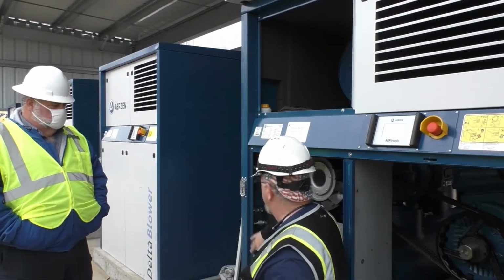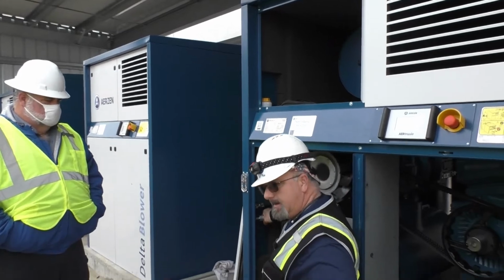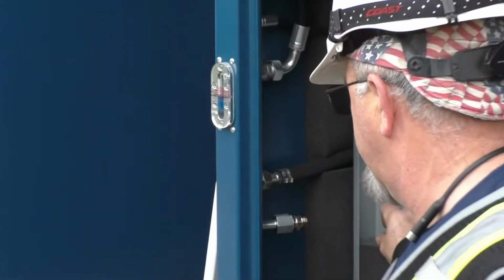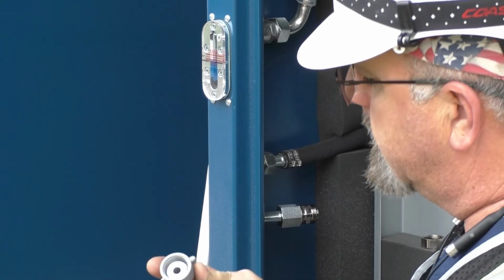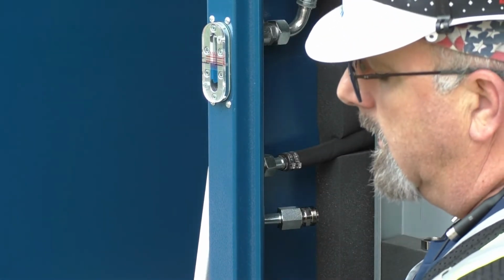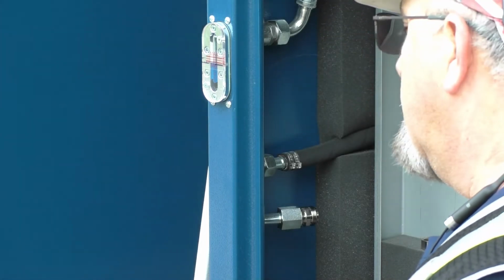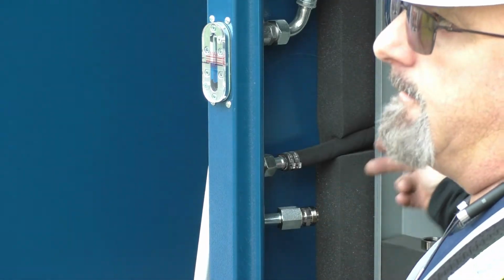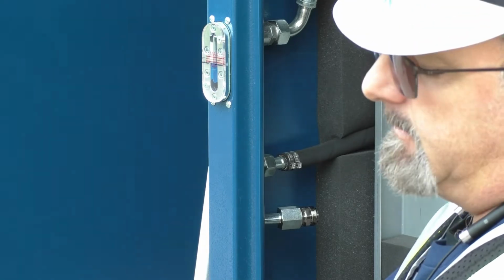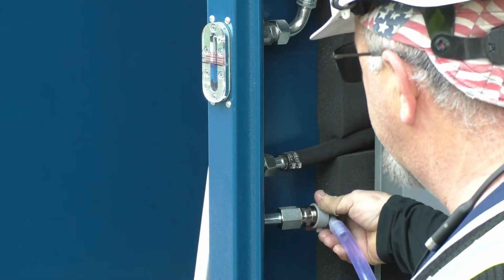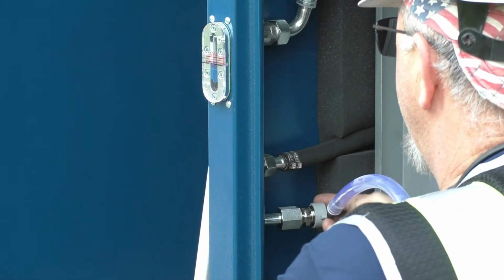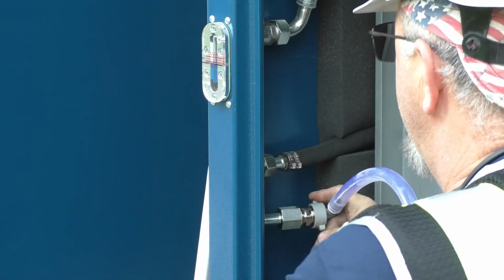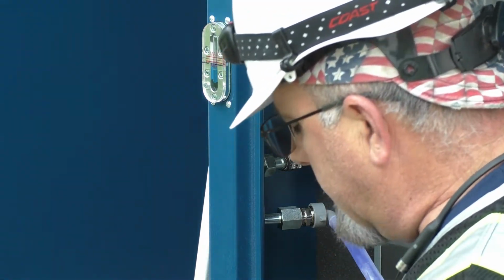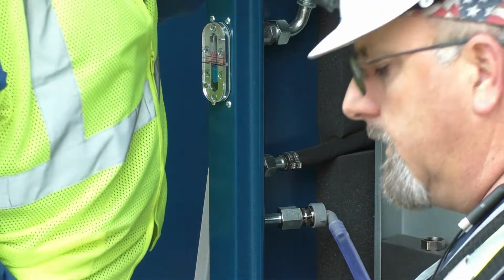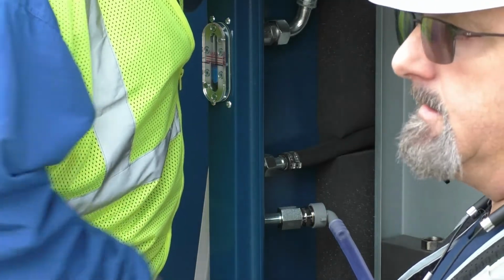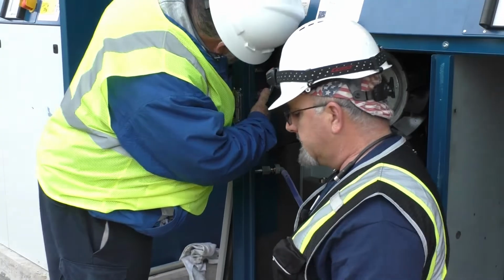So to change the oil, you have this cap here, which should only be hand tight. You have your handy dandy drain hose. It has the plastic ring that screws on. This white ring, if it's missing, what it does is it fits inside this valve to fully push it open and seal it so it doesn't leak around this. So to change it, line it up, start it on there, tighten it all the way down, drain the oil into your sample bottle or your catch jug, whichever, if you're taking a sample or changing the oil.